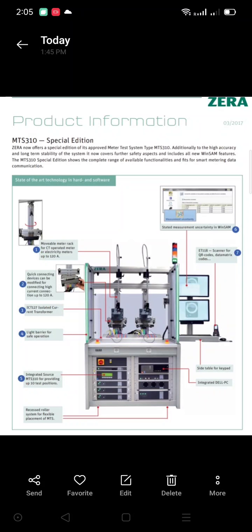Hi friends, today I would like to introduce you a smart, interesting test bench from Zera. It is a test bench for the smart energy meter testing and calibration system. This facility can be used to test, measure, and calibrate, as well as for the certification test of smart energy meters, both single phase and three phase, CT operated or fault current meters. The accuracy of the reference meter here is 0.02, which enables it to measure or calibrate meters from 0.2 S to class 2 accuracy equipment.